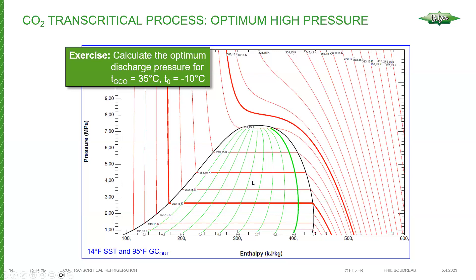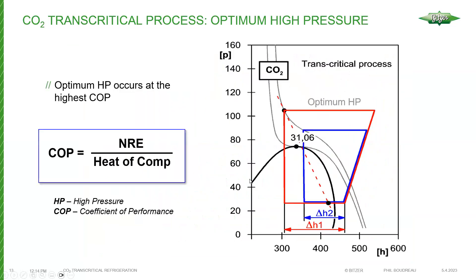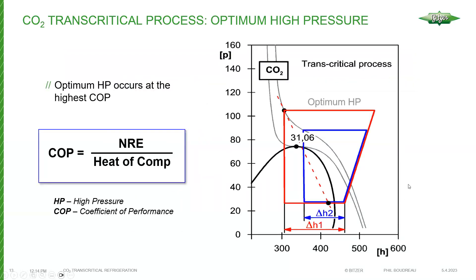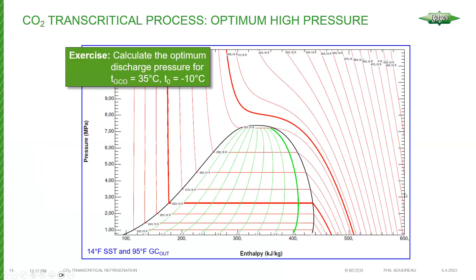Note that the optimum pressure is not necessarily the point where you get optimum capacity. You can actually sacrifice COP for higher capacity — this could be done to facilitate a heat reclaim cycle, for example, or if a compressor is down and the system needs to be forced to get more capacity even at the expense of reduced efficiency.